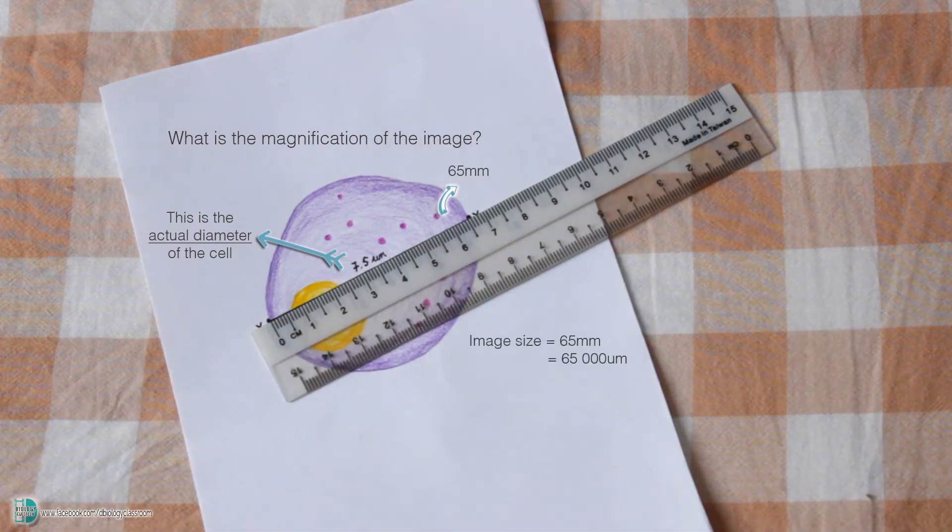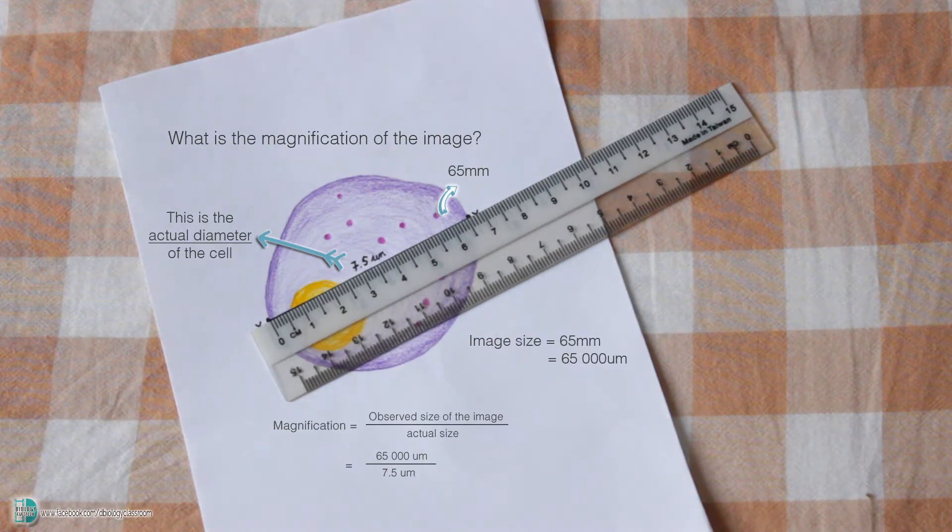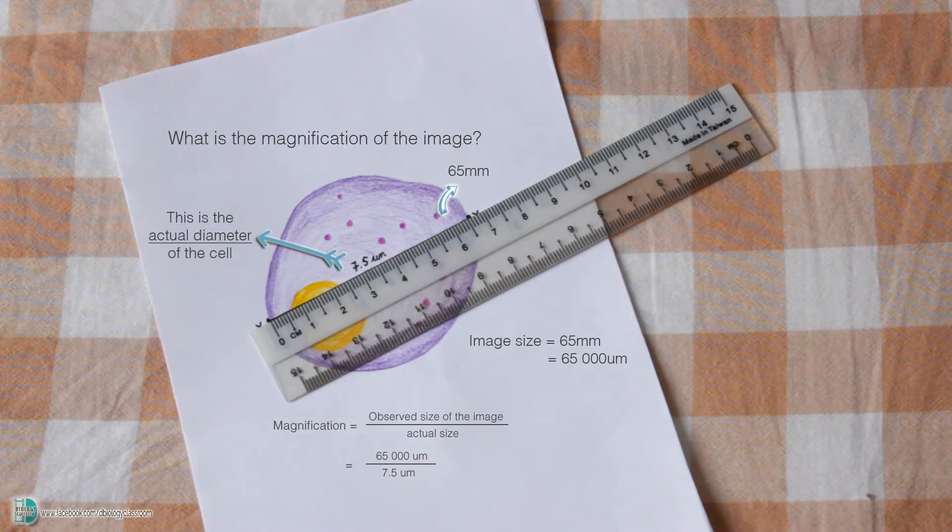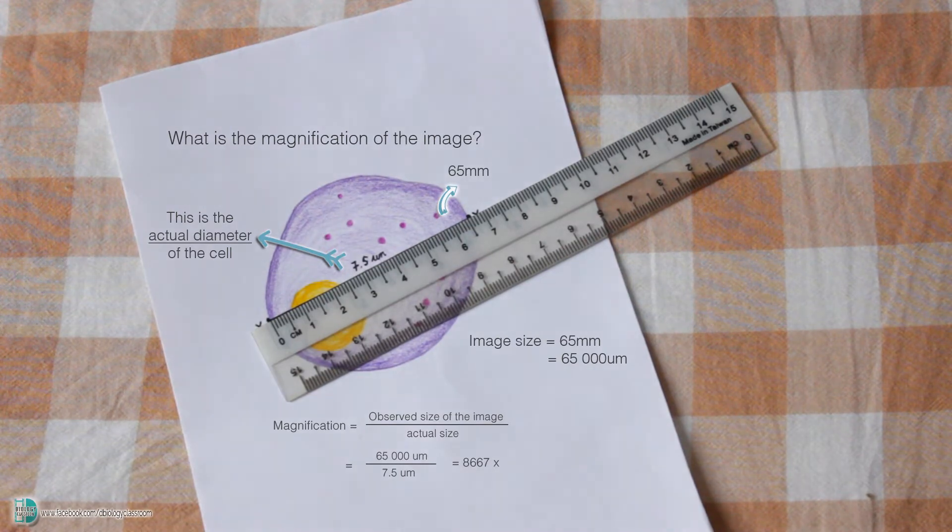Convert it into micrometer. Then, divide it with 7.5 micrometer. You will find out that the magnification of the image is about 8,667 times. Bear in mind that in the calculation, the unit you use for the image size and the actual size has to be the same. That is why I have converted the unit from millimeter to micrometer.